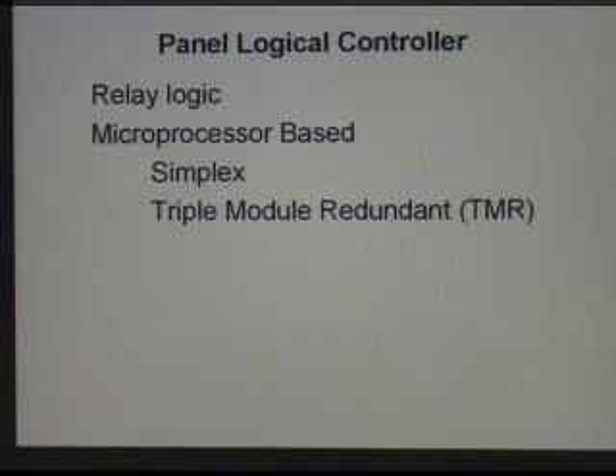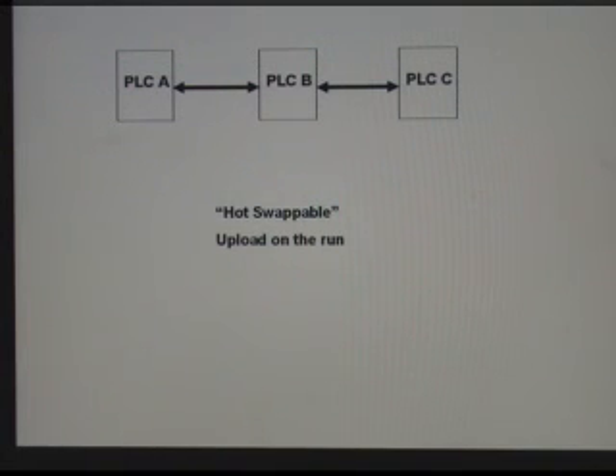So they ended up asking for triple module redundancy, which is called TMR, which means that you end up with 3 PLCs, all of which talk to each other. And they all have the same program inside, and they all supposedly get the same input. So they all do the same algorithms, and they all come up with the same answers, and they constantly talk with each other, and as long as every answer matches, everything is fine. If PLC A comes up with a different answer at some point in time, PLC B and PLC C stay with the same answer, and they agree with each other. These two take control. This one issues an alarm that says there's something wrong with the PLC.